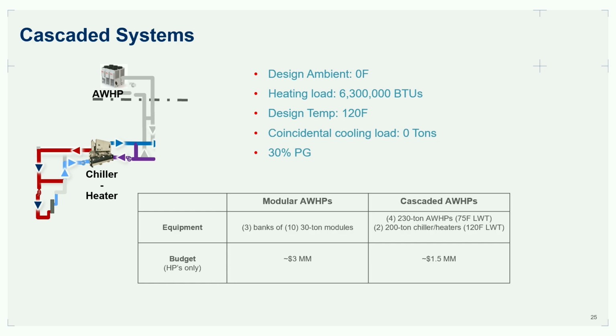On the air source side, people sometimes accuse me of just trying to sell more equipment. That is my job. That is what I try to do. But if you look at the cost standpoint, it actually might make sense from a first cost. And this is a fairly small system, 6.3 million BTUs. If we're just going with specialized equipment that can do that 120 degrees of lift, hey, simple design, COP is going to be about 2, maybe $3 million first cost of the equipment only.